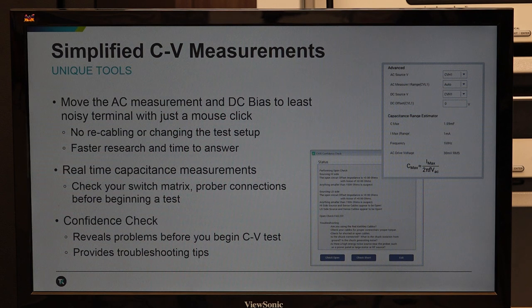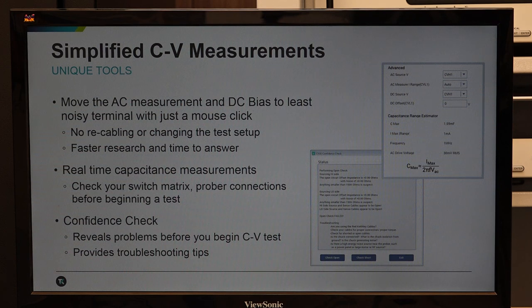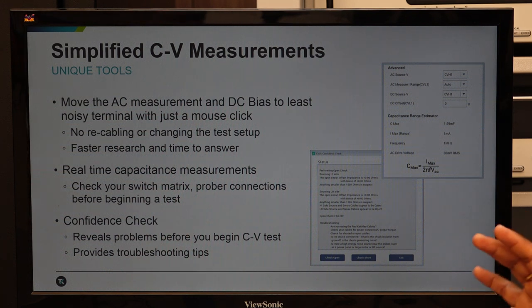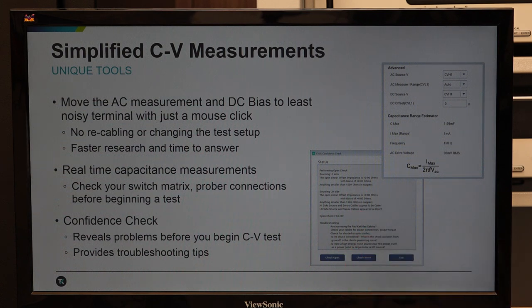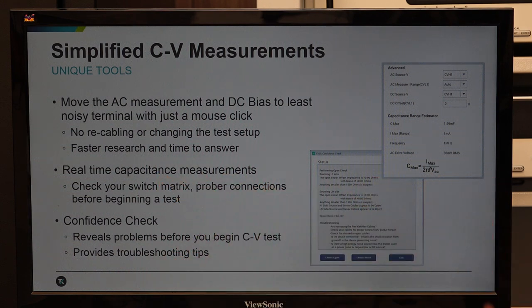CV measurement is more difficult compared to IV measurement. Most of the time, we end up measuring noise instead of directly doing the CV measurement, and it is difficult to find where the noise is coming from. To help researchers troubleshoot, Keithley parametric analyzer 4200 comes with simplified CV measurement unique tools, including real-time capacitance measurement — just make connections and directly get the display, with no need to set voltage sweep or frequency sweep.